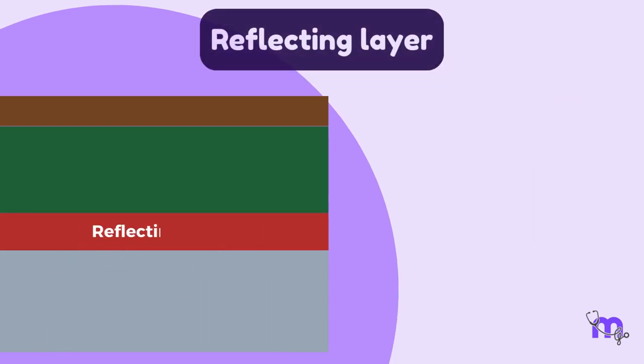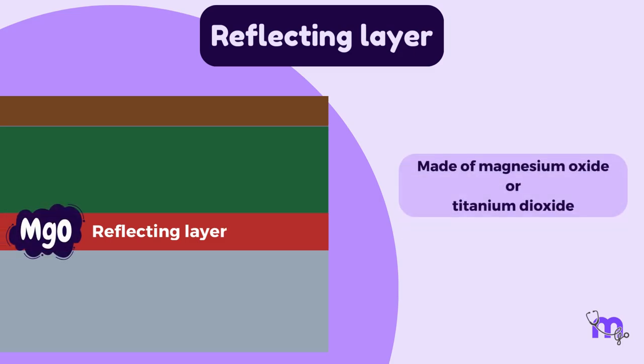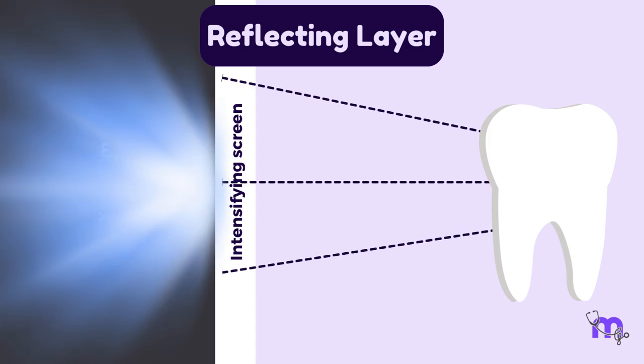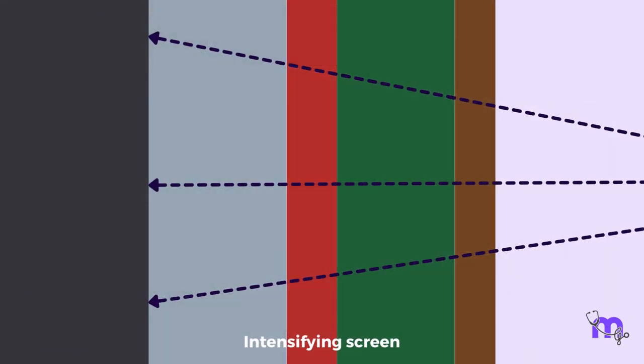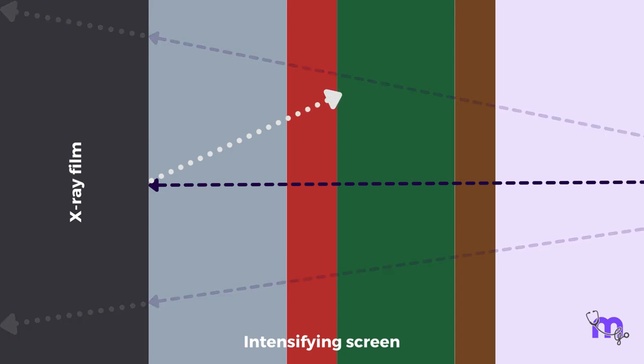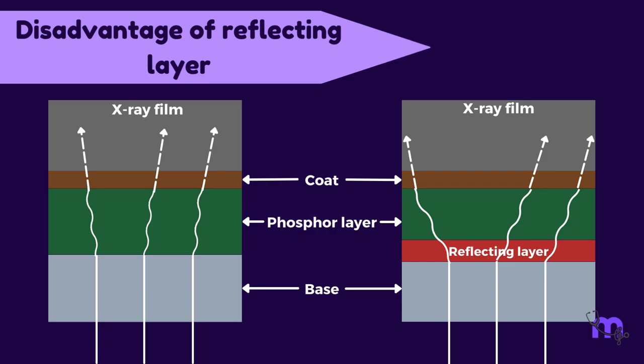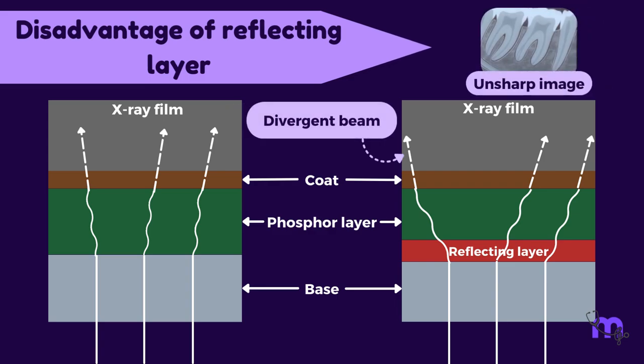Next we have the reflecting layer, made of magnesium oxide or titanium dioxide. Let us discuss its role. We know that the intensifying screen converts X-ray photons to visible light through a phenomenon called fluorescence. Most of this visible light is directed towards the film. However, some of it is directed backwards, away from the film. When this happens, it comes in contact with the reflecting layer, which redirects it back to the film. Although the reflecting layer has a significant role, it has one disadvantage. The light it reflects is more divergent, resulting in an unsharp image.